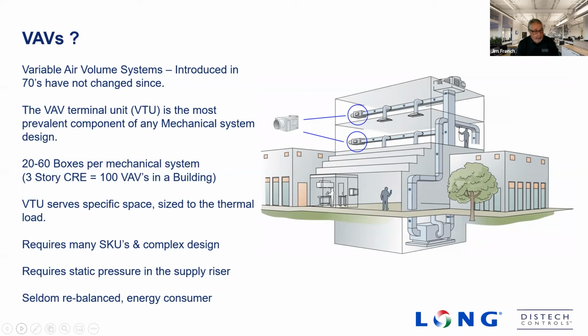A couple of other things about it, Cutter, it requires static pressure in the supply riser. Many of these systems require 1 inch to 3 inches of pressure to operate. And with pressure comes noise. And acoustics are a challenge with these systems, and keeping the noise in tolerable ranges for customers.